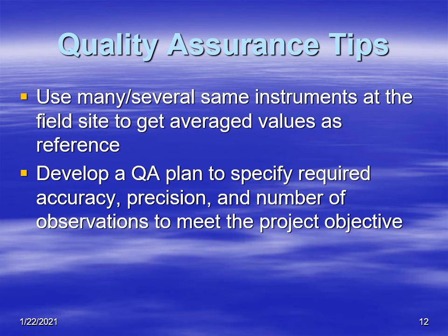And then you should have a quality assurance plan, of course, that talks about the measurements, the procedural standards that you're going to have. How do you collect the data? How do you average the data? Do you measure the data to the nearest hundredth of a degree Celsius or tenth or just 1 degree Celsius? All these things need to be decided before you go out into the field and start making measurements.